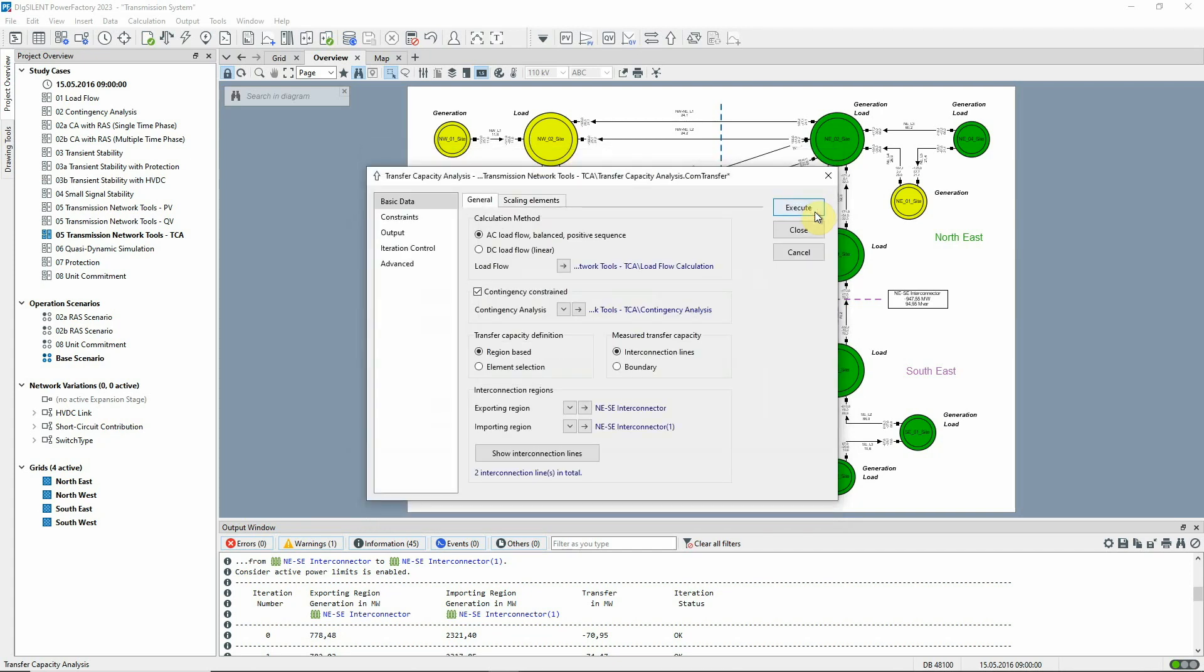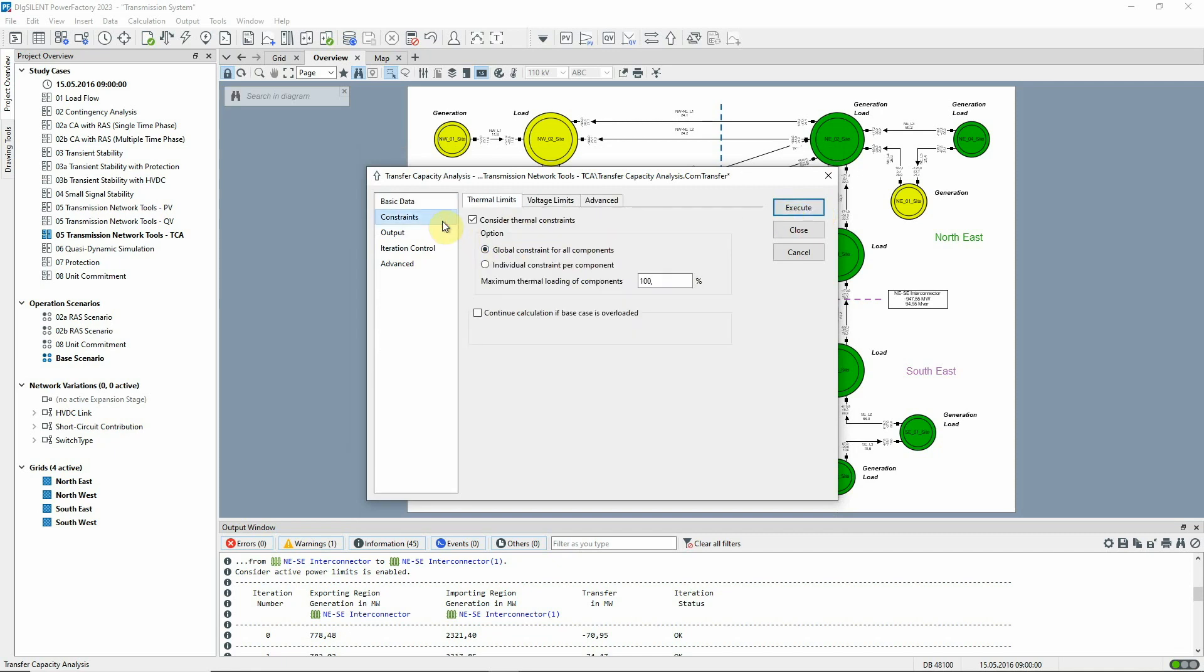Before executing the analysis, there is a further consideration. It's likely that elements overloaded due to faults will be able to exceed their thermal rating for a limited time, provided that post-fault actions to reduce the overload are available. For this reason, we will increase the maximum thermal loading of the components to 150%.